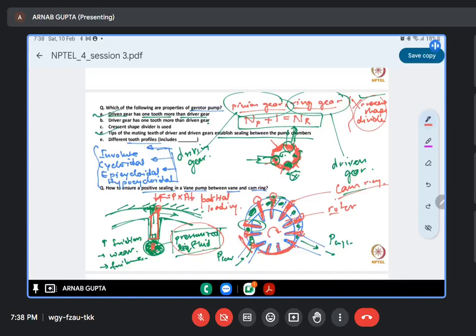Okay, and there are other types of vanes also. Here also the wear component may become high because of the pointed tip. So for that, sometimes we use a dual type, like two bevel vanes like this. So these are a few things that are done as precautionary measures while we are using some pressurized hydraulic loading here, and that hydraulic loading is done to provide a positive sealing.